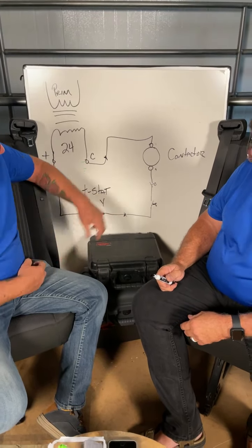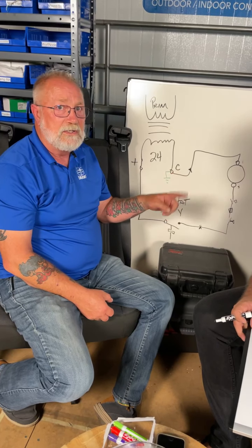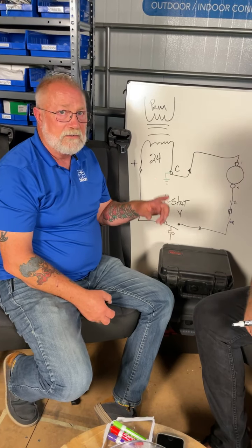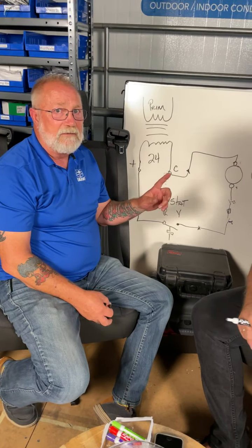So the reason we did this is if you're looking at the furnace or air handler and you're looking at that board, take your readings from Y to C on that board, and that will tell you whether or not you actually have 24 volts going out to the condensing unit. And you do the same thing with G to C. If you want to know if you've got your 24 volts, you go from R on the board to C on the board. And if you don't have a board at the furnace or air handler, then where the thermostat wires all connect, there's a bundle of wire, but you should have a board in today's technology.